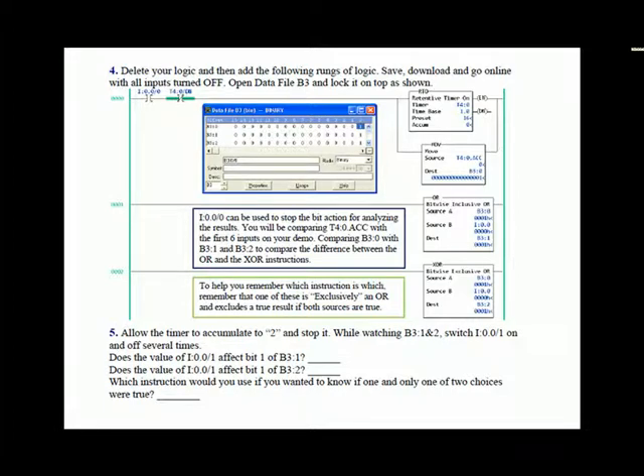Here we have a little bit different logic. We have a retentive on timer, which allows you to start and stop a timer and have it stop at an accumulate value. If this were a TON, if you made the rung go false, it would reset to 0. This gives you an opportunity to cycle a value basically 0 through 15, even though the preset is set to 16. You can pause it anywhere you want by simply turning off input 0. And when the timer is done, it stops. Allow the timer to accumulate to 2 and stop it. While watching B3:1 and B3:2, switch input 1 on and off several times.